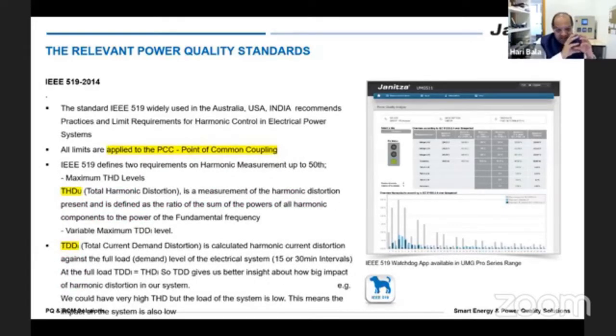Now, I am just taking you on a travel inside IEEE 519. The standard is widely used in Australia, now in India, and the USA. It recommends good practices. It gives good limits. It supports the consumers who are generating harmonics, because a lot of loads are high frequency, switching loads, which means there can be a high amount of harmonics getting into the system. At the same time, it supports the utilities, in that the consumer should take the responsibility and the utility should monitor the voltage harmonic distortion from their side as well. That is why CEA also mandates that distribution companies should have power quality meters in their outgoing feeders, in their distribution substations. That's another subject, which is currently going on.